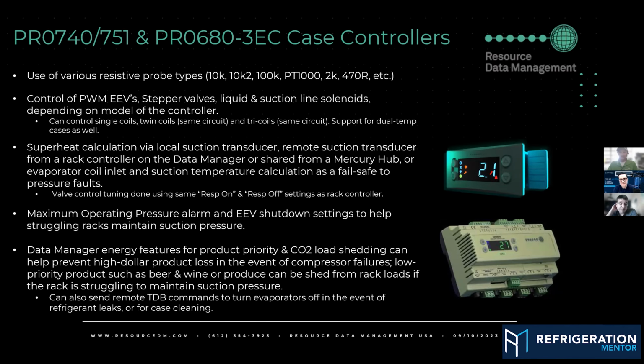James, when you talk to James Darby, I think he touched on this, that you can use either local pressure transducers, or you can use a remote pressure transducer reading from the rack. If you're doing a remote transducer from the rack, I'd say make sure you always check with gauges at your suction, at your case. Make sure that there's not a pressure differential there. I'll see people use remote rack pressure and then they don't even check, and then you might be off several pounds, which is going to throw your superheat off, and maybe you have flood back if it's really bad.